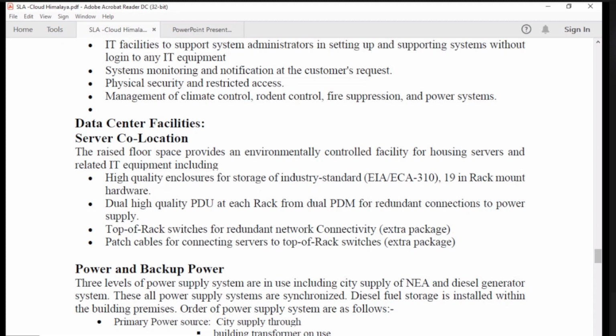So two power sources, two power units, PDUs. Rack from dual PDU for redundant connections to power supply. Top of rack, so we are not using middle of rack or end of rack. It uses top of rack switches for redundant connectivity, and patch cables for connecting servers to top of rack switches.